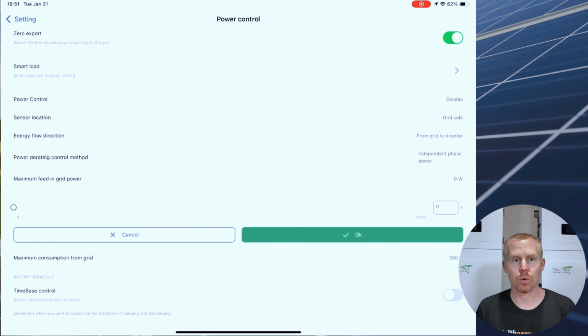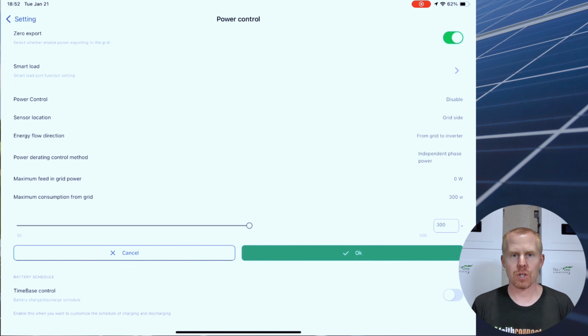Maximum feed into grid, that's if you're selling back to the grid. I am not. So I have zero export enabled up above, and then I have this value set to 0. This allows you to basically set in watts how much power you want to allow to push back to the grid. Maximum consumption from the grid.